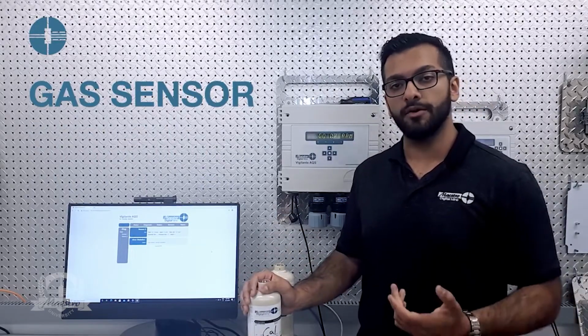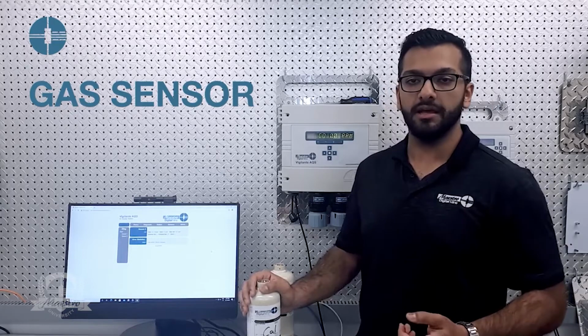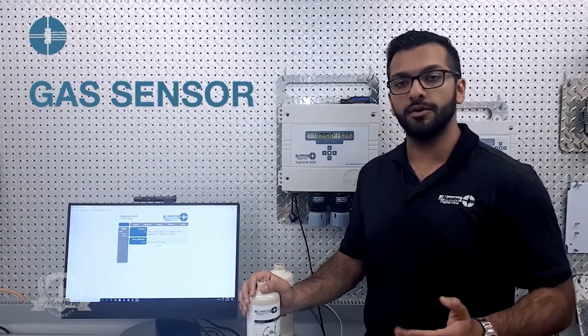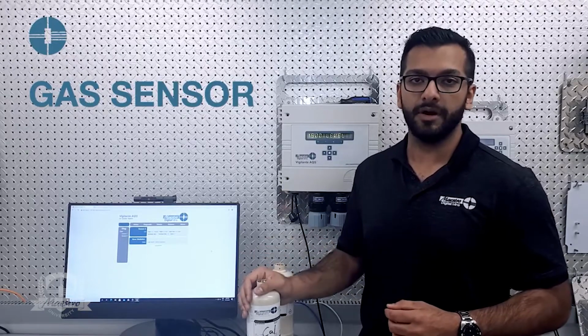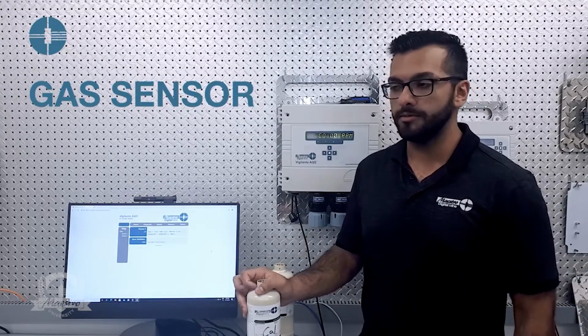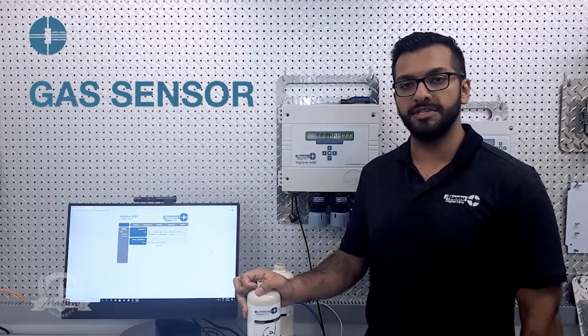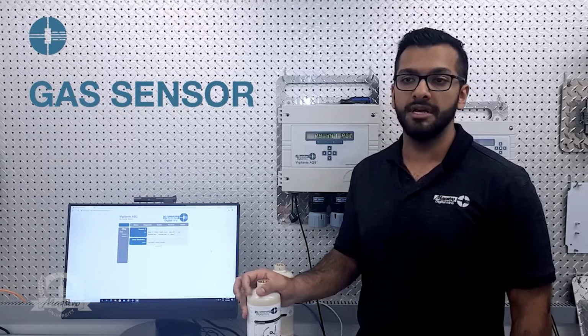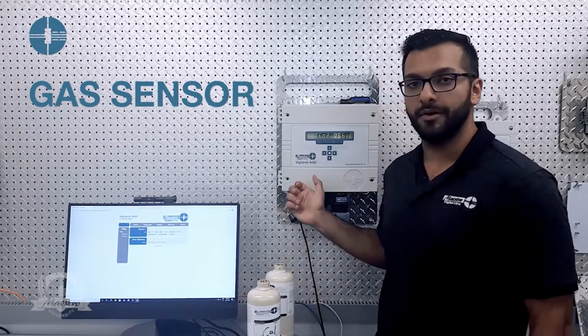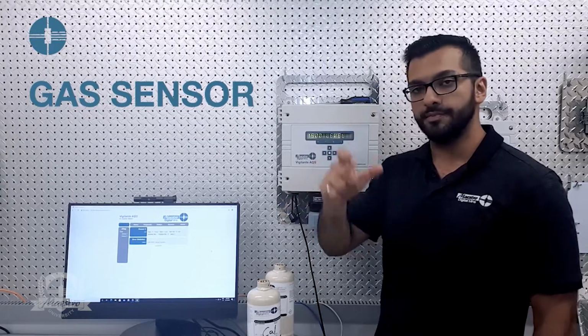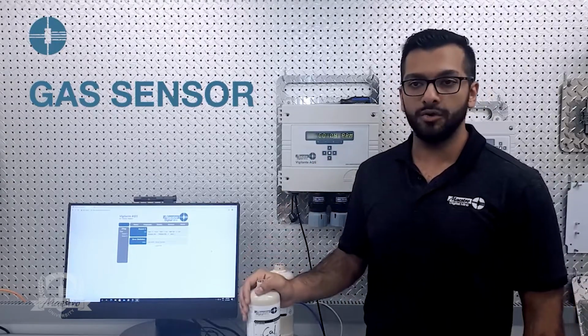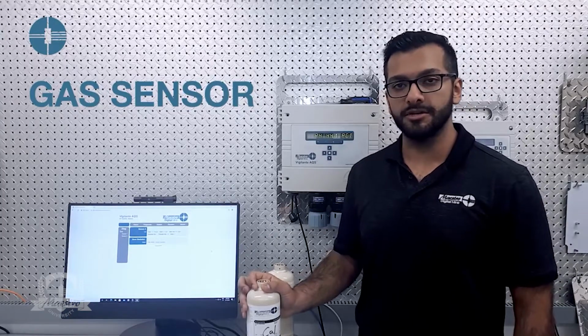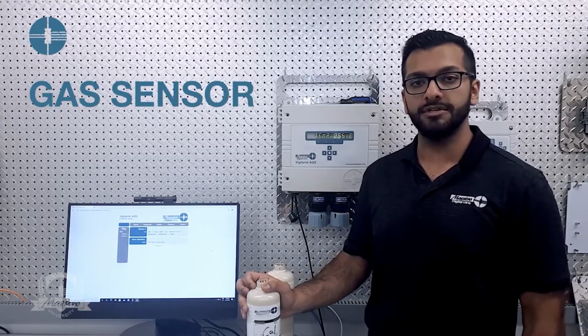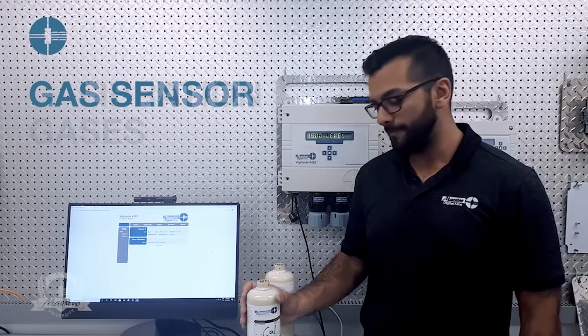So we have a CO sensor here, and according to the warm-up table, the long power off time, which is if you haven't powered on the sensor for, let's say, a minimum of a week to 3 months. Sometimes they're used as backup sensors and they haven't been powered on for a while. For that warm-up time, you need to allow the sensor to stay powered on for at least 2 hours. Whereas if your sensor has remained powered on, like what we have here, and you just power it on and do a hot swap, and you want to recalibrate that sensor, all you need is 5 minutes for the CO sensor, and you should be good to either use it or use it for calibration.